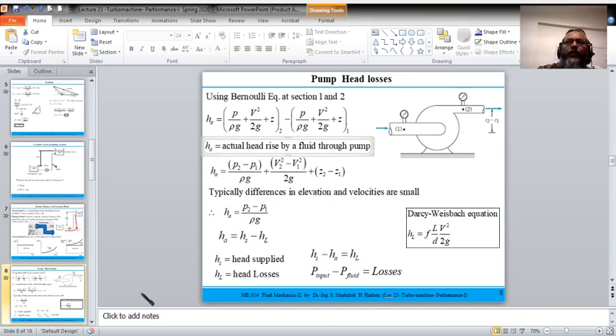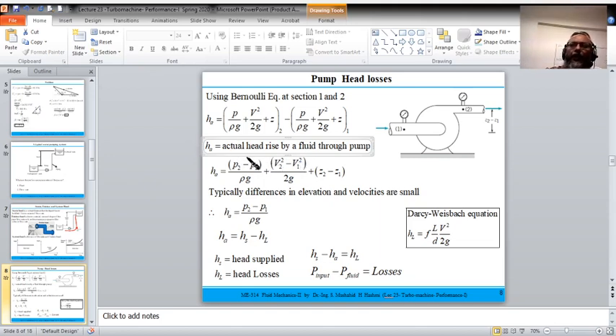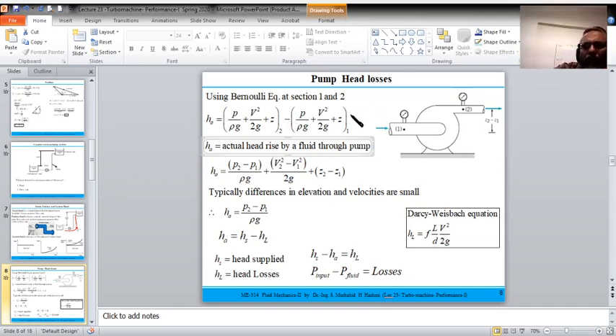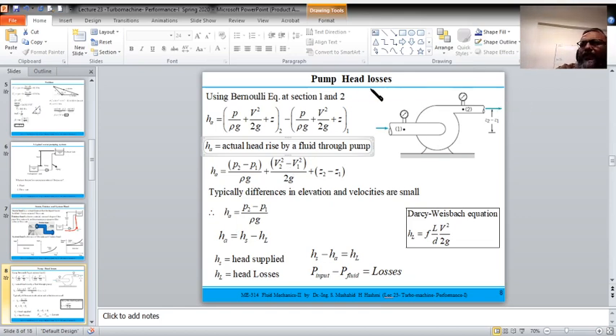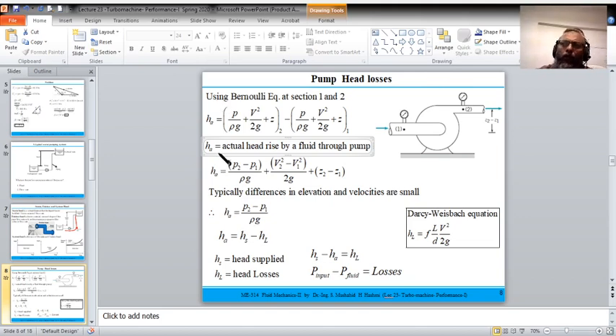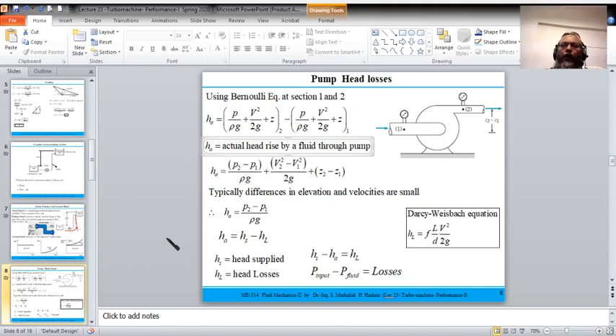The actual head ha equals the difference in pressure head, velocity (kinetic) head, and potential head between outlet and inlet. If the changes in velocity and elevation between suction and discharge are small and ignored, then ha simplifies to the pressure difference: ha ≈ (p2 − p1) / (ρg), or equivalently Δp = ha · ρ · g.